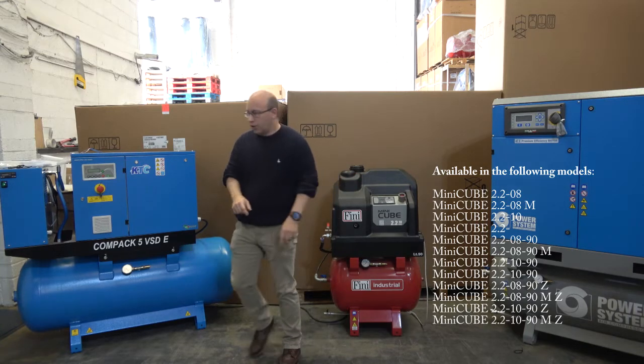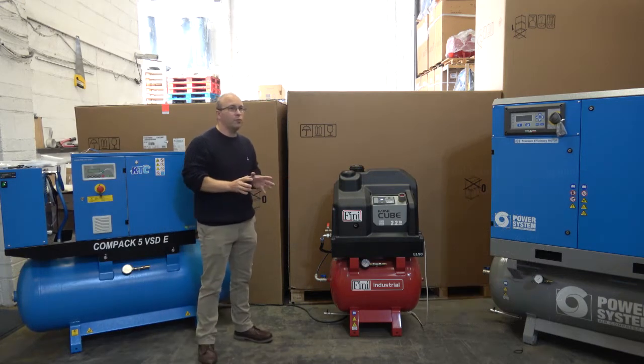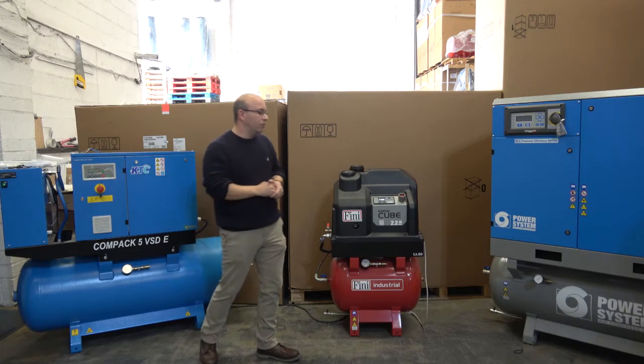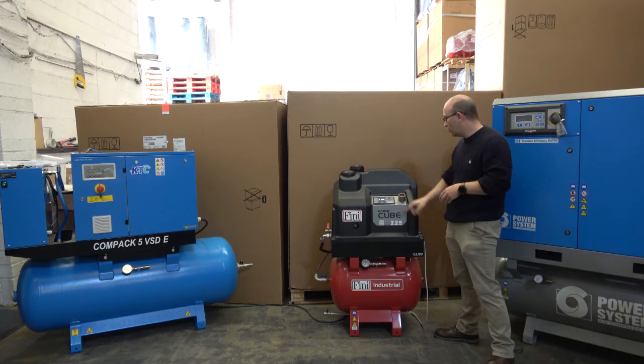I'm going to power it up and run the unit, but then we'll take the lid off so you can see the inside of it. This particular unit we've actually retrofitted with an adsorption dryer on the back end of it, because we knew there would be certain applications where a desiccant dried supply of air would be useful. I can confirm that we will actually see a minus 30, almost hitting a minus 40 dew point of pressure on the back end of it as well.